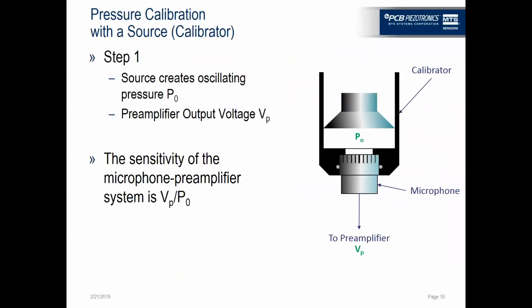So again, we're just going to go through this again with the graphics in here. These graphics will outline a little bit of what goes on inside the mathematics and mathemagics of how to do a calibration. You have a sound source that creates a known pressure. We usually look at these numbers in decibels, but these also are equally as valid in pascals and volts. You have a preamplifier output voltage. And if you don't care about anything other than that system voltage with that microphone, with that preamplifier, the sensitivity of the microphone preamplifier system is the voltage output of the preamplifier divided by the pressure input of the sound calibrator.